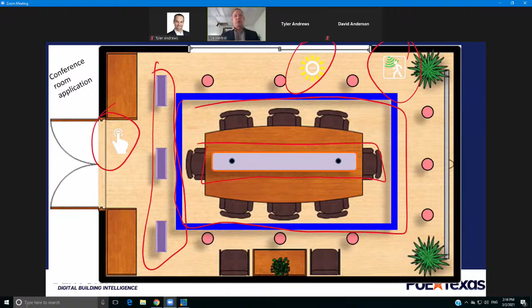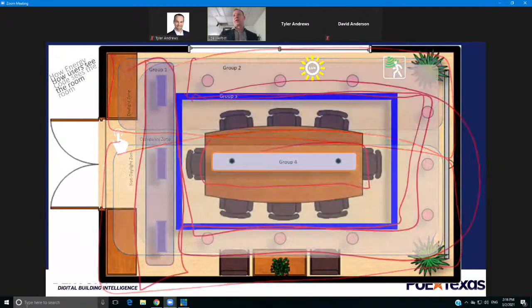So what does that look like? Essentially, to do this I have a phase dimmer attaching a circuit to these four downlights, with a single controller since it's in a daylight zone. I've got a 0 to 10 to these two fixtures, and then a different set of controls for the other downlights and the cove lighting.